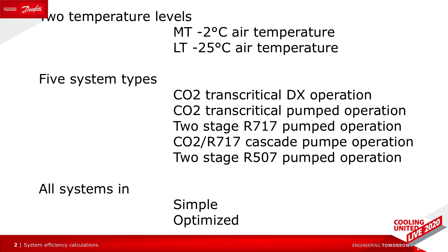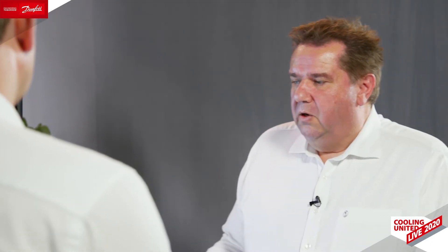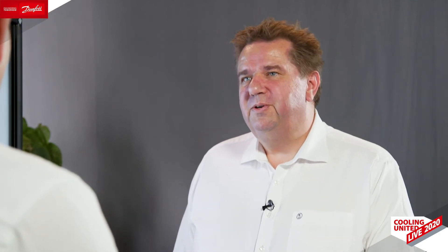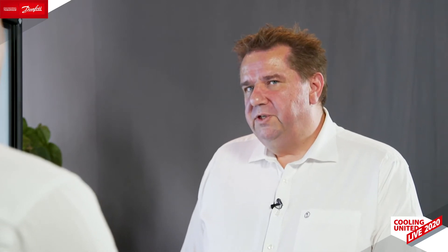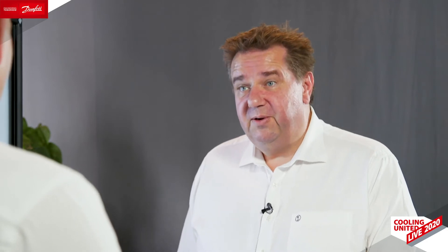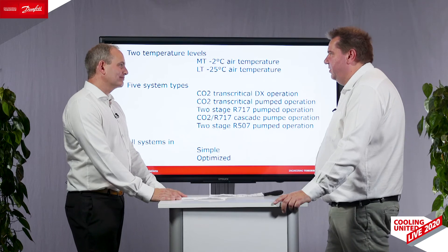We decided to model five different systems: CO2 transcritical in a DX operation mode; CO2 transcritical in flooded or pumped version; a two-stage ammonia system in pumped operation as it normally is; a CO2 and ammonia cascade, again with pumped; and finally, for a backwards comparison, a two-stage R507 also with pumped. All of the systems were calculated in a simple version — a bare-bone system, basically the cheapest that you could find and install.